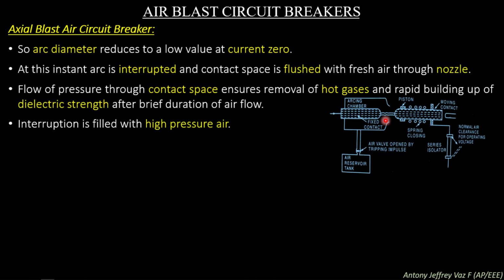The interruption chamber is filled with high pressure air. So during this process, the interruption of the arc occurs due to high pressure air. The dielectric strength of air increases with air pressure. So if we want to increase the dielectric strength, we need to increase the pressure of the air present in the air reservoir tank.